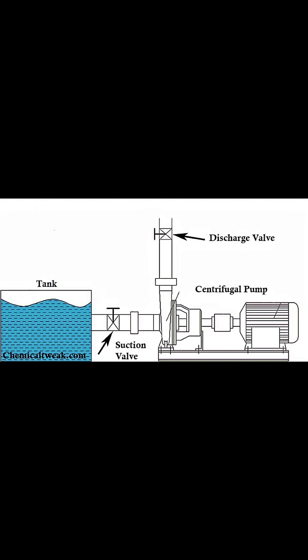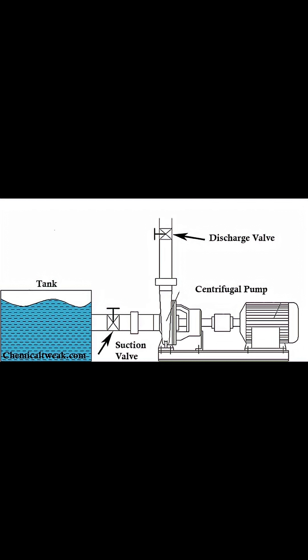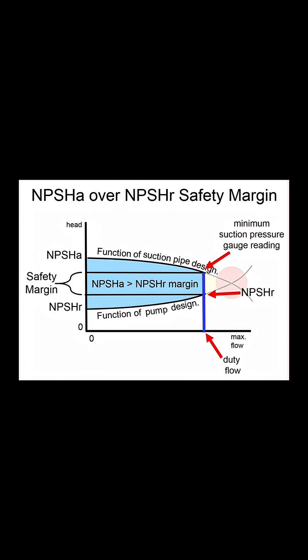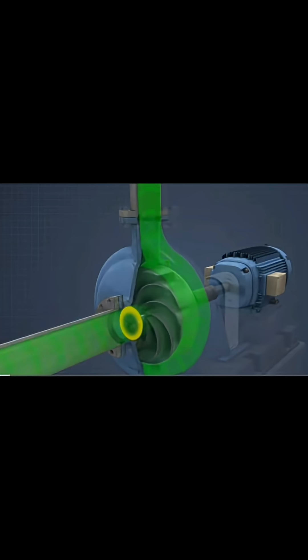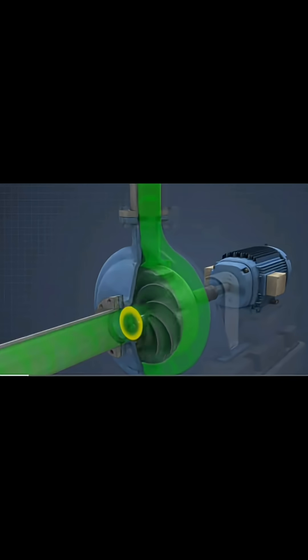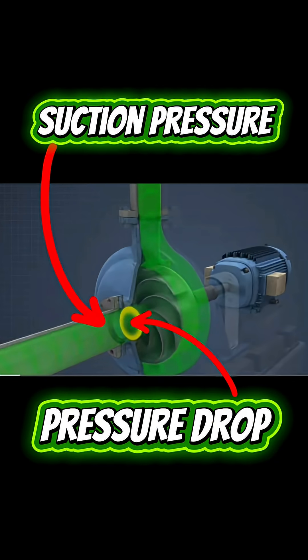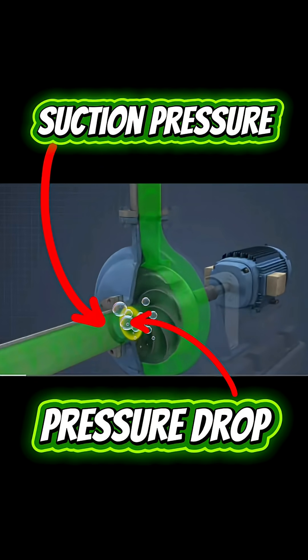Suction cavitation is a little different. To understand suction cavitation, we must first understand what net positive suction head, aka NPSH, is. NPSH is a measure of the pressure available at the pump's suction to prevent the liquid from boiling and turning into vapor. The NPSH required is determined by the manufacturer or the NPSH chart. There is always a pressure drop as the liquid enters the pump's suction eye and is accelerated. If the NPSH available drops below the NPSH required, the pressure at the suction eye drops below the liquid's vapor pressure, essentially creating a vacuum and causing it to boil. In other words, there must be enough pressure on the suction so that this pressure drop doesn't cause the pressure of the liquid to drop low enough to cause the liquid to boil. The NPSH required is calculated to ensure this doesn't happen.